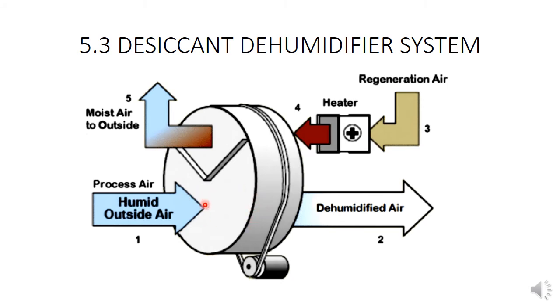And of course this desiccant, after long use, when it has achieved its absorption limit, we need to regenerate the desiccant. The regeneration of this desiccant is done by warming up the desiccant using a heater, and the water will evaporate and be channeled to the outside, so the desiccant will be dry again and can be used again for dehumidification of air.